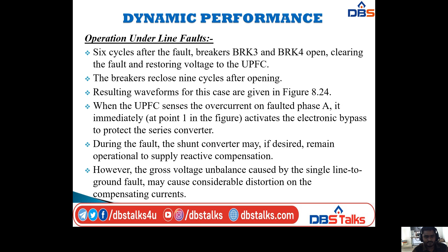So these waveforms show normal fault clearing conditions, that is, the previous waveforms, where the fault current is conducted by the electronic bypass switch.